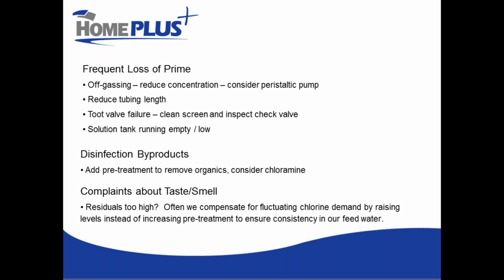Anything that is not allowing the solution into the line, deposits can cause this. And that foot valve has a little check valve, a one-way valve in it that prevents the solution, when the pump stops pumping, from falling back into the solution tank. If that valve has failed, you will definitely see more frequent loss of prime. So check that valve out and make sure it's operating correctly. Water should only flow through it in one direction, or chlorine. They're not very expensive to replace. And of course, make sure you're not running out of solution. If you run out of solution, you're going to start potentially drawing air in there, which will often cause a loss of prime.